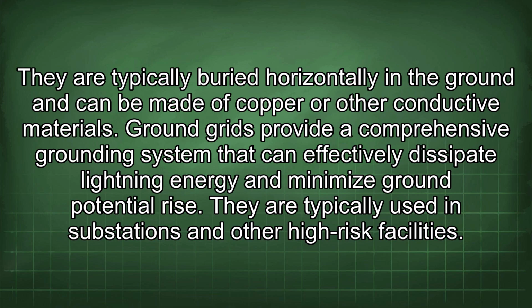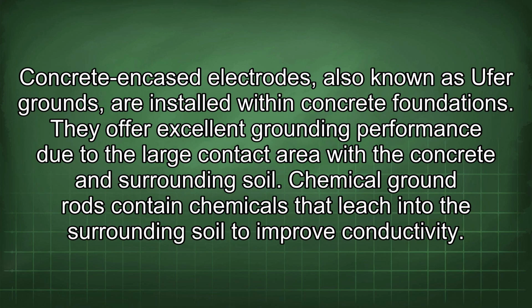Ground grids provide a comprehensive grounding system that can effectively dissipate lightning energy and minimize ground potential rise. They are typically used in substations and other high-risk facilities. Concrete encased electrodes, also known as UFER grounds, are installed within concrete foundations. They offer excellent grounding performance due to the large contact area with the concrete and surrounding soil.